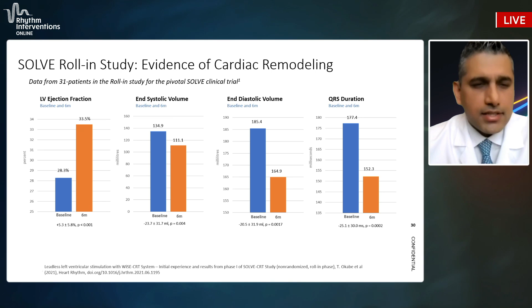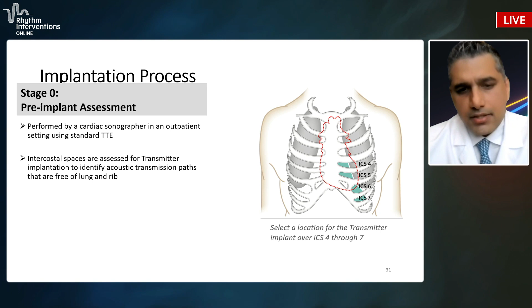So the implantation process for this WiSE CRT is a 2-stage process, and it does require screening, just like sub-Q ICD. In the screening, you use a standard ultrasound probe to look for a window without lung and rib in the intercostal space, and usually it's from intercostal space 4 to 7. Once the patient passes the screen, stage one is the implantation of the transmitter and battery. I usually prefer to do it a day prior to the electrode implantation, but some centers prefer to do it in the same setting.